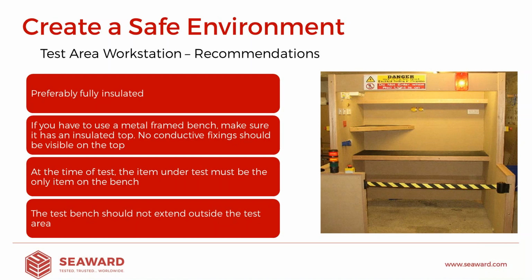What we shouldn't be doing is having loads of tools or spare parts lying around that, again, could invariably create a path to ground. So the operator comes along, decides he needs a particular tool, he goes and picks that up, and fortuitously that's just in contact with a live part. Again, he could be putting himself at risk. So always make sure it's just the item and the test equipment needed at the point of doing the test. And then again, to ensure that nobody can come into contact with it, always ensure that your test bench itself doesn't extend outside of the test area that you've designated for safety.